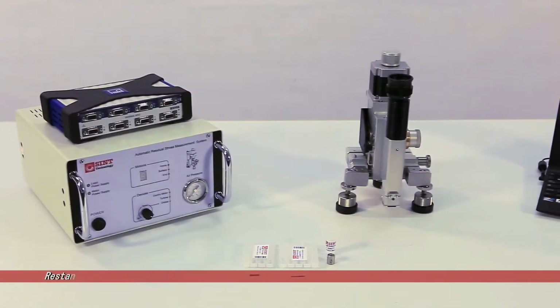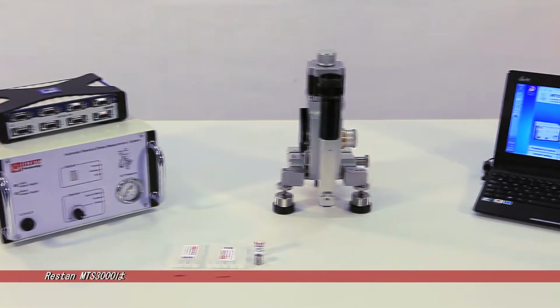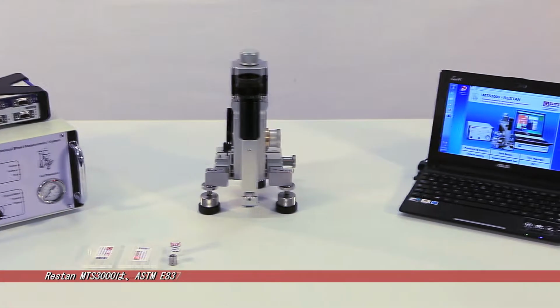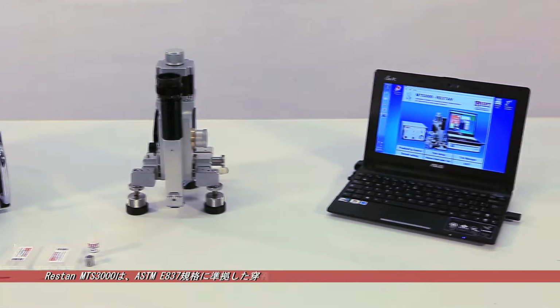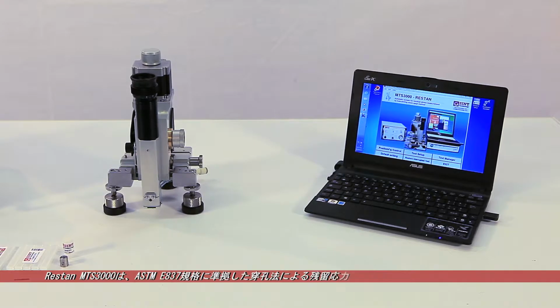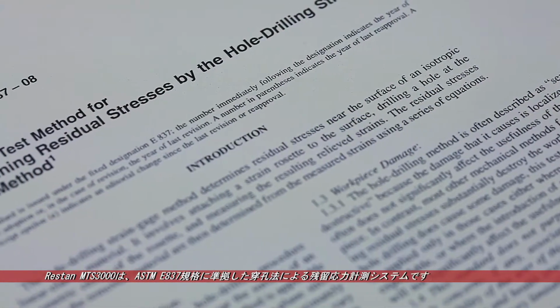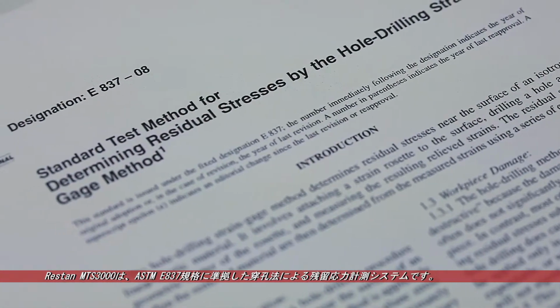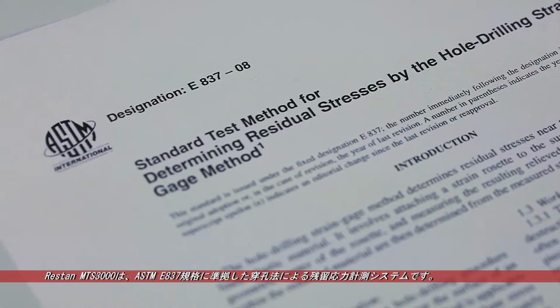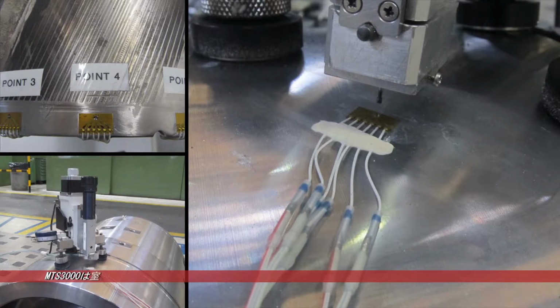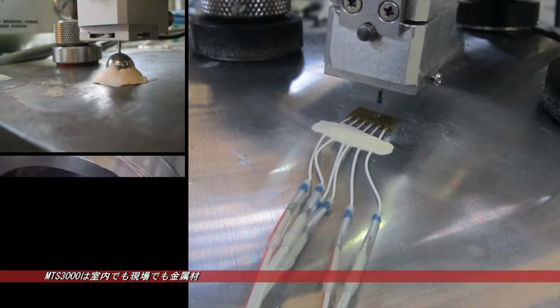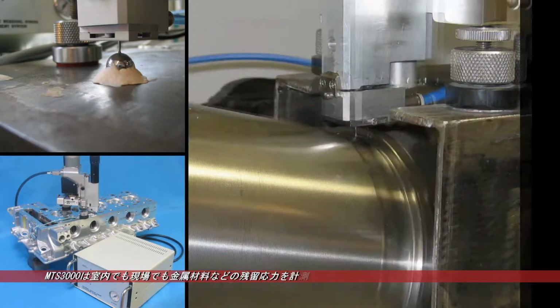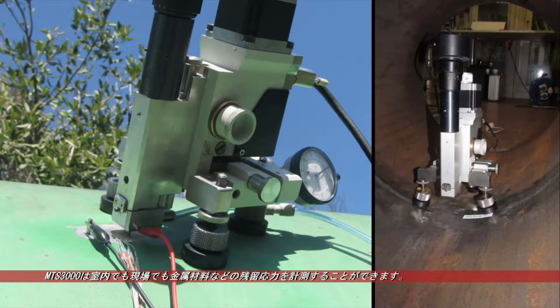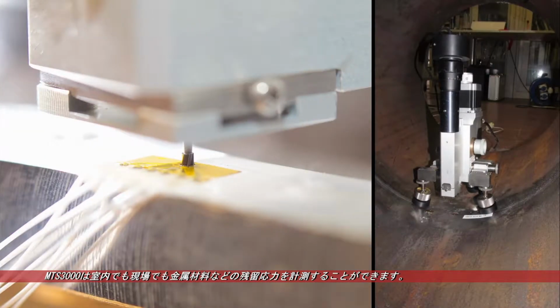The Restan MTS3000 is an automatic device for measuring residual stresses by the hole drilling strain gauge method, in accordance with the ASTM E837 standard. The MTS3000 is able to measure residual stresses in metals and other kinds of materials, both in the lab and on site.